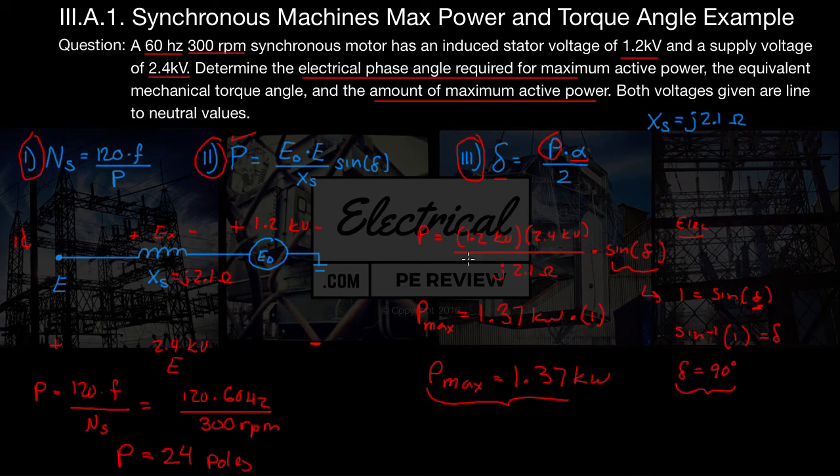I think it's time to solve for alpha. I'm going to rewrite that to solve for alpha. We can say alpha equals delta times 2 divided by P. All I did was I solved for alpha. We already know what delta has to be for maximum power. We found that to be 90 degrees. So I've got 90 degrees times 2 divided by our number of poles we just found to be 24. We punch that in our calculator, and we come up with an answer of 7.5 degrees.